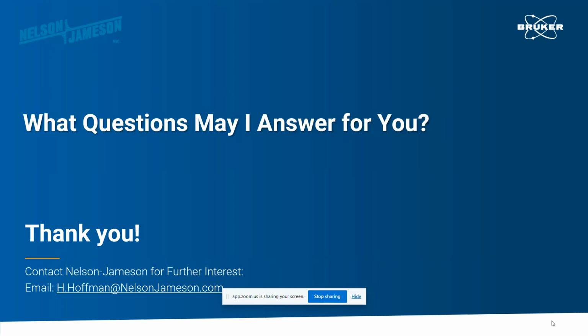Yes. For this process, we are here to assist you through every step. So if you're working with a product that can be accurately measured by NIR, we typically like to be in the loop on that, and we'll assign an application scientist to work with you. Sometimes it comes down to further developing or modifying an existing calibration you may be looking to utilize, where we'd only need to roll in some of your data to create a model that represents your product. So it's good to keep us in the loop, because we might have existing data or calibrations that can help you. If you're curious about the exact number of samples needed, that comes up a lot, but there isn't a set number I can give, because it really depends on the application. For instance, you need to take into account the expected variation of the product you're working with and the range that needs to be accounted for, because those factors have to be represented in order to have a robust calibration that can predict those sample types.